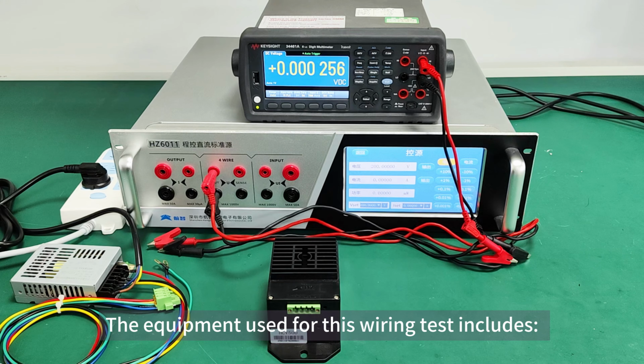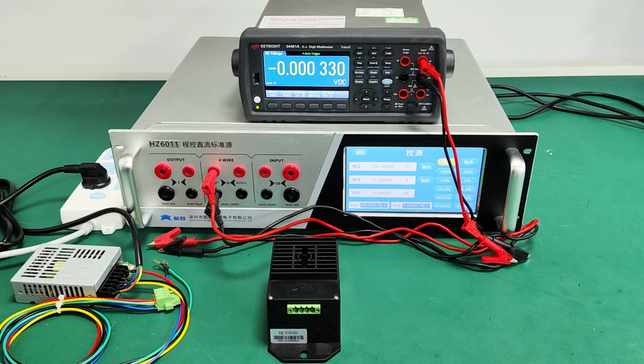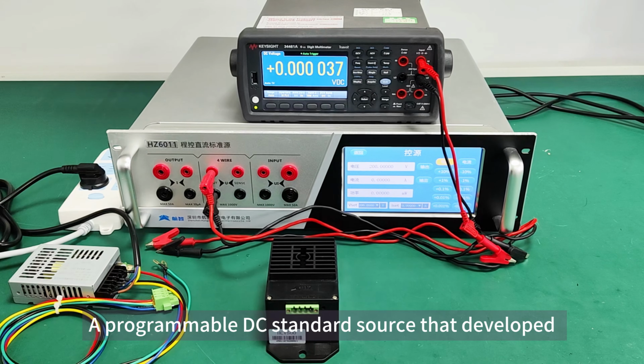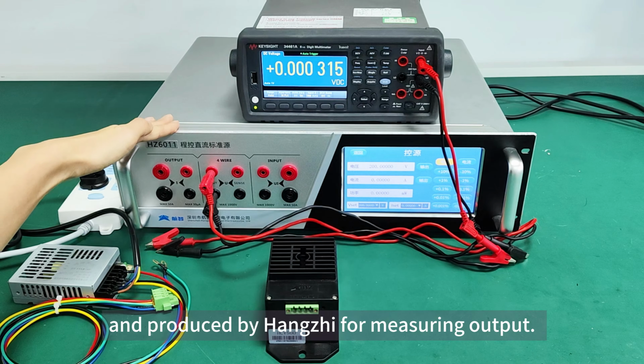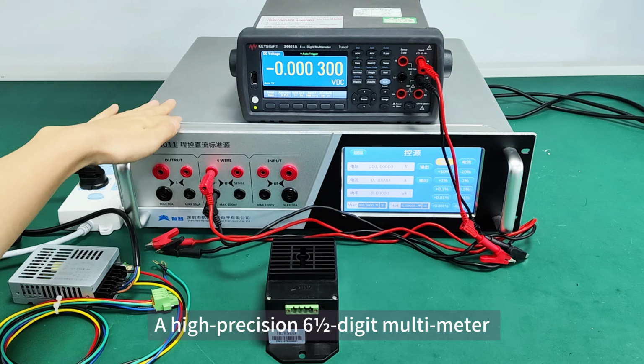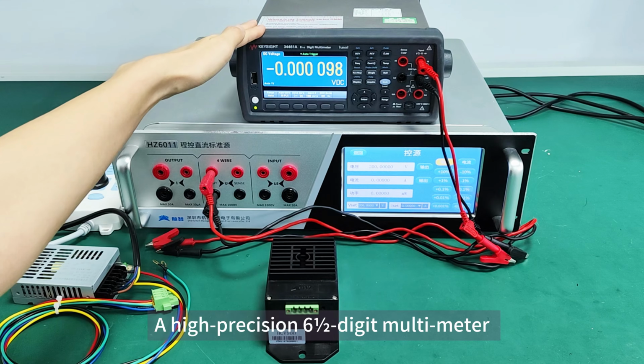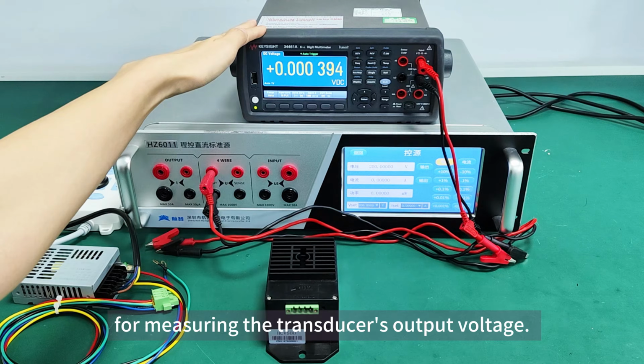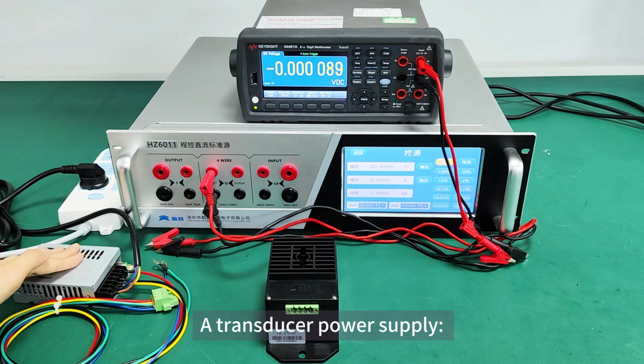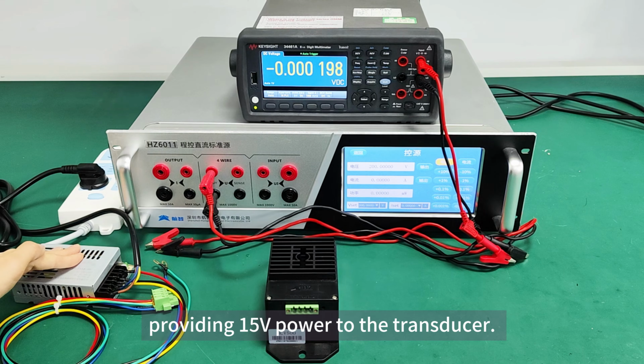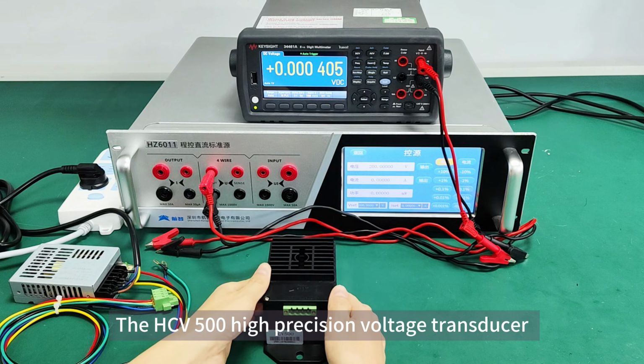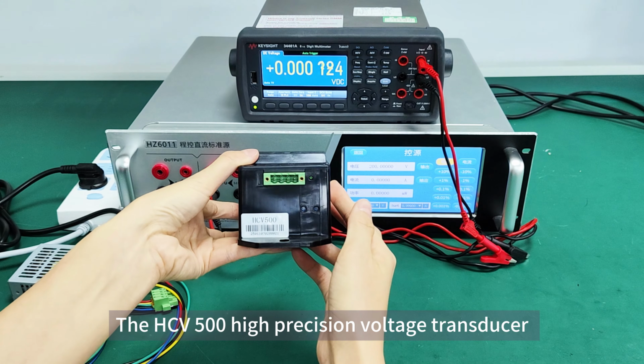The equipment used for this wiring test includes a programmable DC standard source developed and produced by Hangzhi for measuring output, a high-precision 6½-digit multimeter for measuring the transducer's output voltage, and a transducer power supply, providing 15 volts power to the transducer. The HCV500 high-precision voltage transducer.